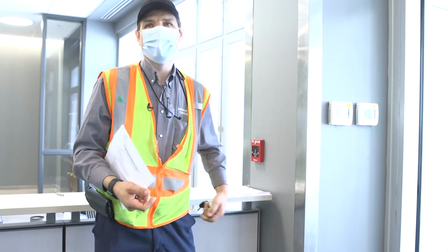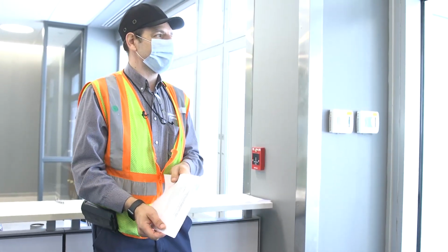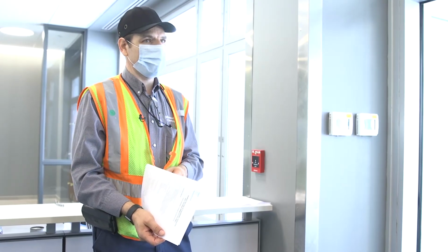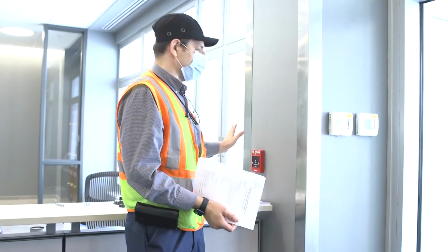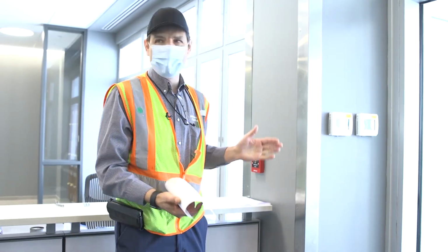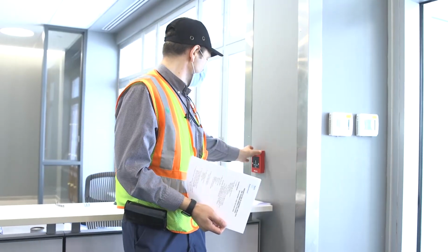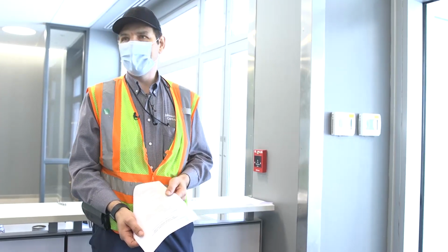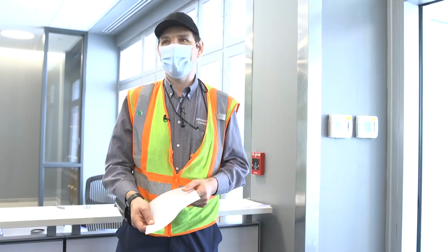And you can hear: channel 7, device 31, testing. So that means this is M7-31. That's the address of the device. That means it's responding to the panel, it's communicating. And this way you can check every device basically like that.